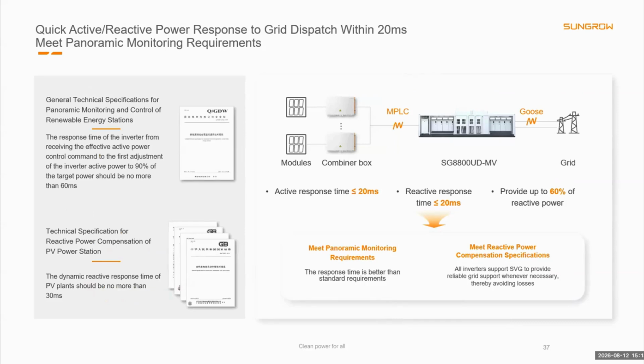The OnePlus-X inverter provides active and reactive power response within only 20 milliseconds. It can also provide up to 60% reactive power and operate in SVG mode when required. This fast response supports grid regulation and helps meet increasingly demanding grid code requirements.